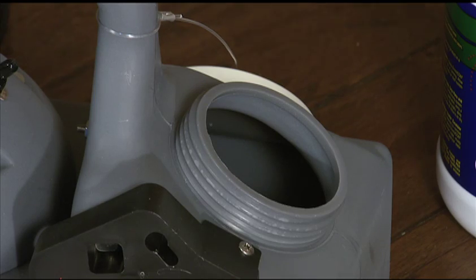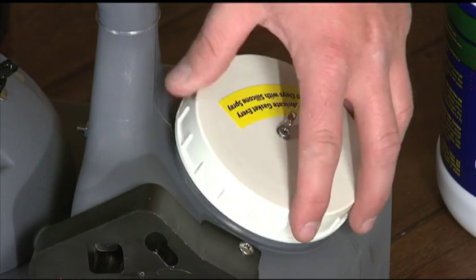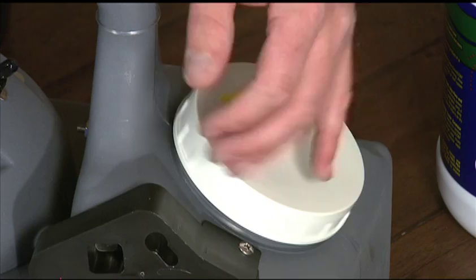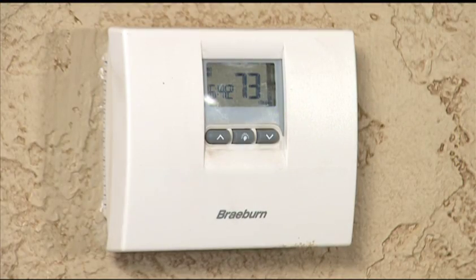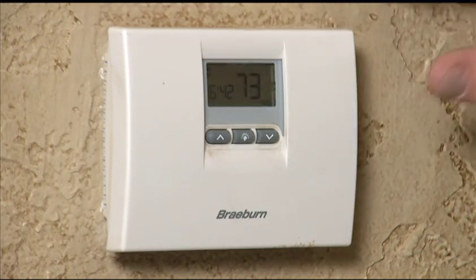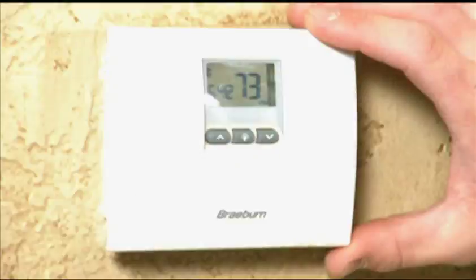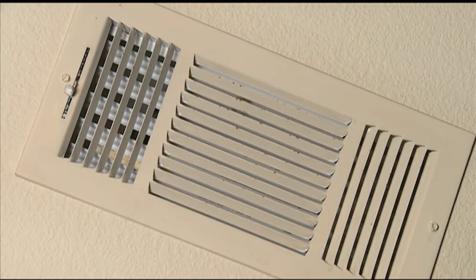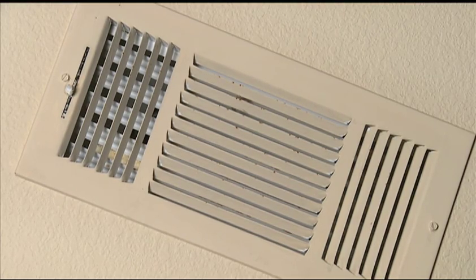Typically, the rule of thumb is 45 to 60 seconds per 1,000 square foot of room space is how long you'll fog through the return. What you need to do is turn on the fan on the air handling system. Not heating, not cooling, just the fan only, and that's controlled by the thermostat itself. What you're going to do is then go to each return and simply take the fogger.